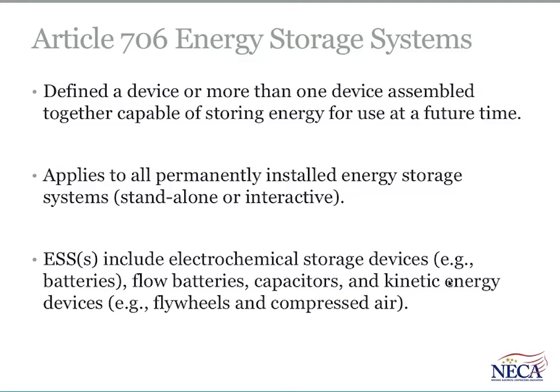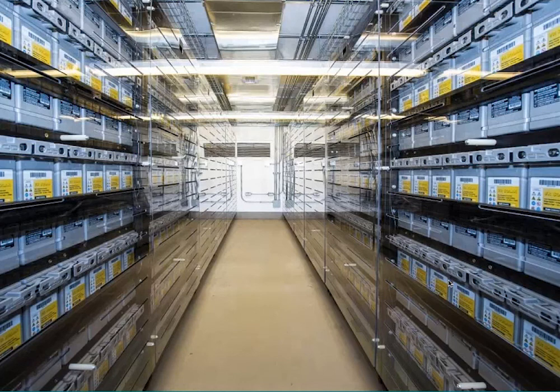Article 706 is brand new, and it's titled Energy Storage Systems, and the common one we're seeing right now in the business is batteries, all sorts of battery technologies, whether it's lead acid, flow batteries, nickel cadmium, which is a kind of older technology, but lithium ion, lithium polymers, and there's other new technologies. But this covers all of that, and it also has coverage of electromechanical storage systems, which could be capacitors or supercapacitors, flywheels, compressed air, and so forth. So the NEC is being equipped nicely with rules to apply to these energy storage systems, which is a key component of handling demand response, taking care of smart grid initiatives and so forth.